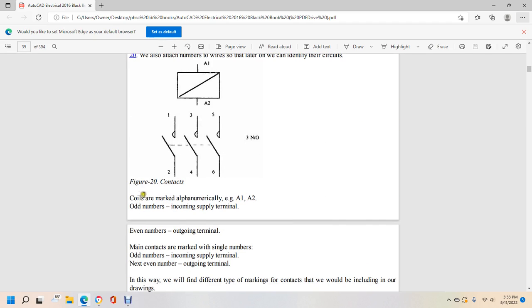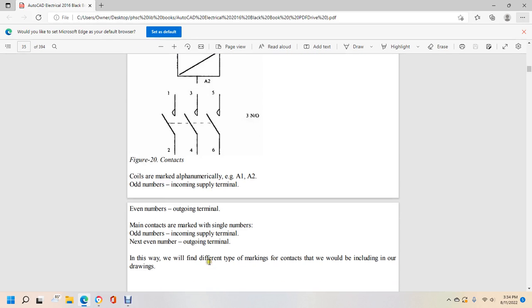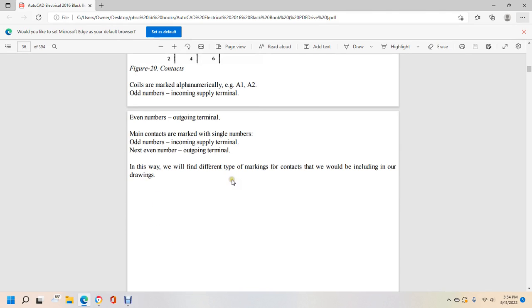Figure 20 shows the contacts for the coils are labeled alphanumerically, A1, A2. Odd numbers incoming supply terminals, even numbers are outgoing terminals, and main contacts are marked with a single number. Odd numbers incoming supply terminals. Next, even numbers are outgoing terminals. In this way, we find different types of markings on the contacts that we would include in our drawings.